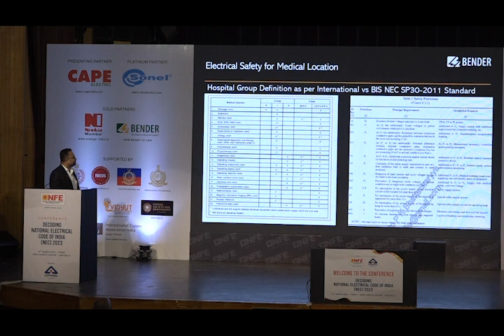So this is the basic difference between two power supply systems. In the grounded system, single phase is given inside the OT. So what will happen during the operation if any equipment malfunctions? The short circuit current, or fault current rather, can go through the patient's body and the doctor's body, and in that way the patient and doctor can get shock. However, in the IT system, which is a non-grounded, floating power supply system inside the OT, there will be no fault current path through the doctor's and patient's body. It can be safe.